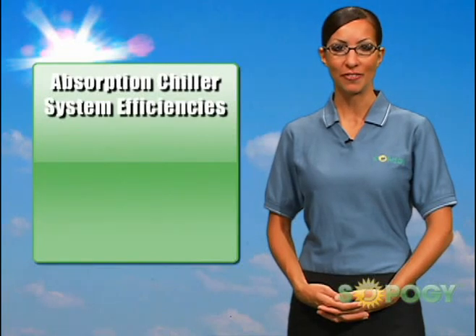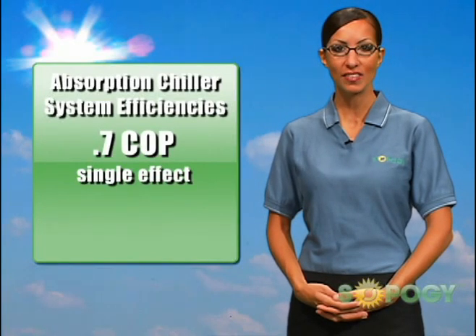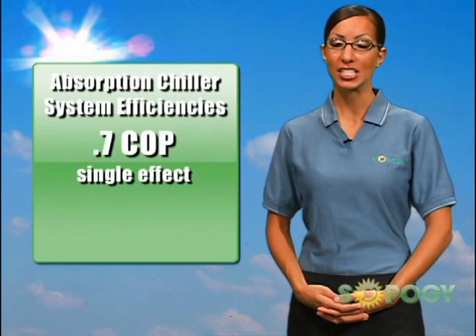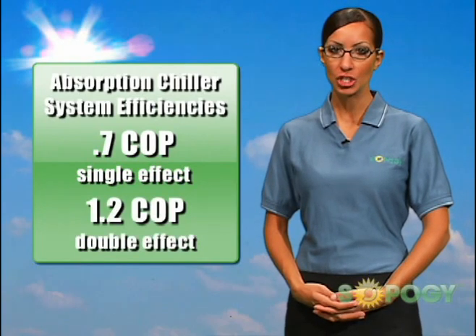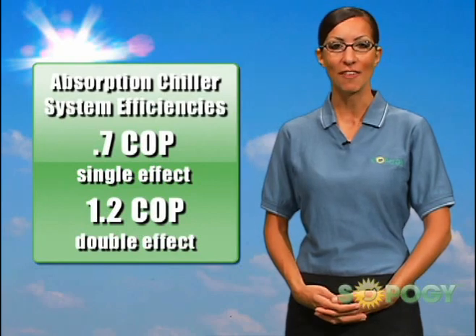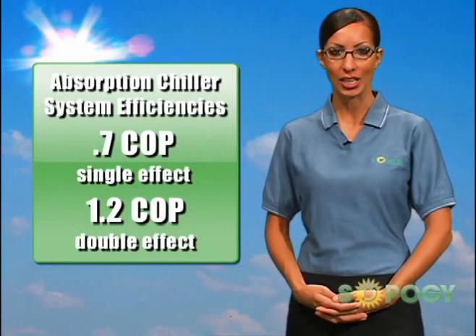Absorption chiller system efficiencies are often around 0.7 COP, or coefficient of performance, for a single effect, or 1.2 for a double effect absorption chiller, making for a good complement to the efficient Sopogy Micro CSP Solar Collector.